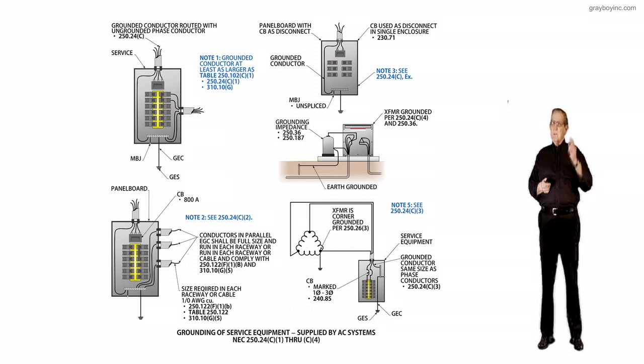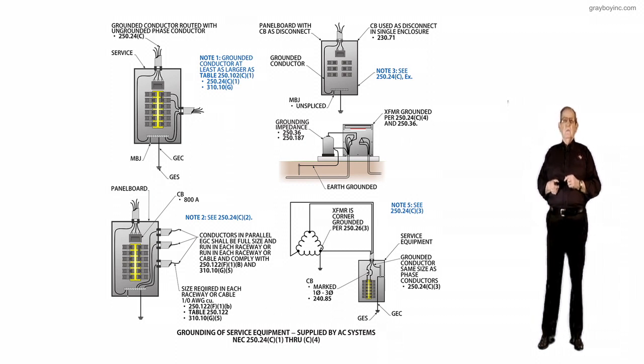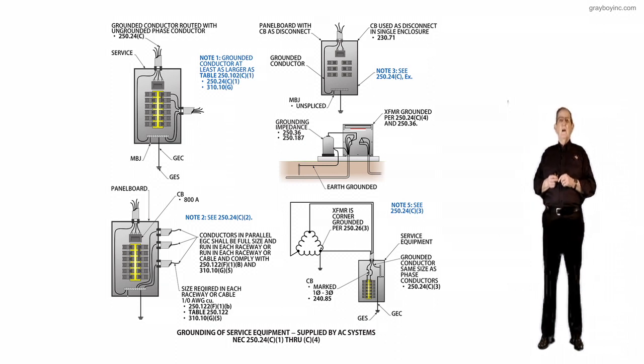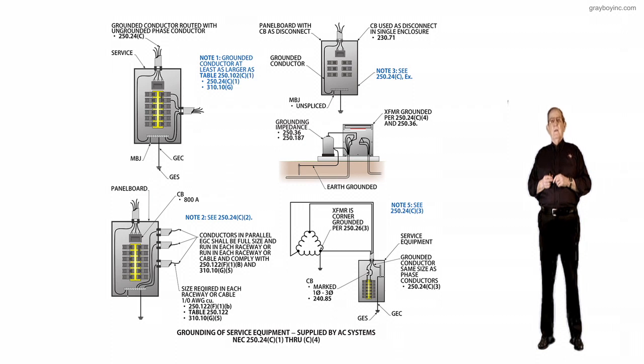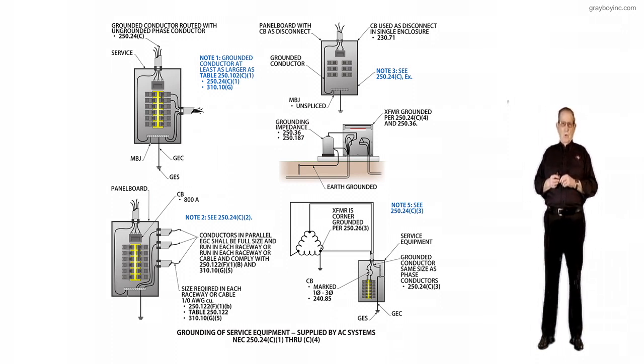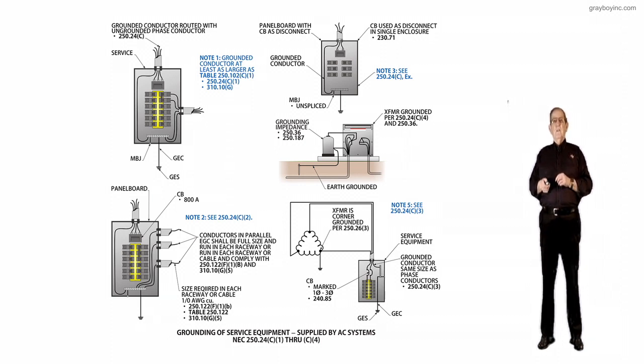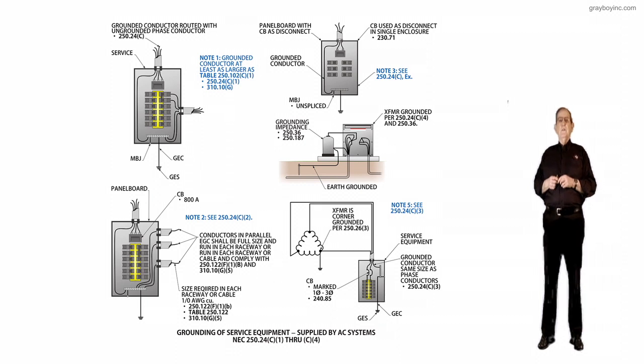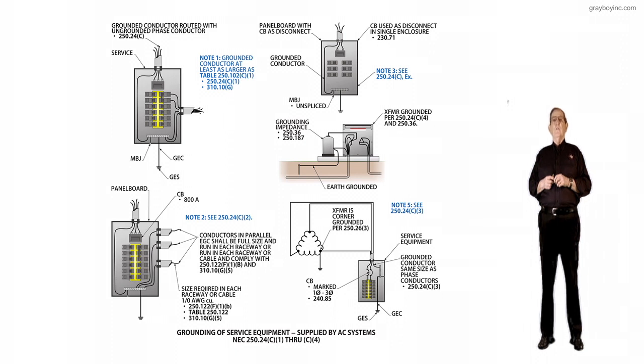Now, if my memory serves me correctly, if we have a 600 amp main, then those conductors would have to be probably about number 1 from Table 250.122 to serve as an equipment ground. If there were neutrals there, they would have to be at least 1/0 or larger. And then at the very bottom of the illustration, it shows you the size required in each raceway or cable: 1/0 or larger if you're dealing with the grounded neutral conductor. But if it's an equipment ground, then 250.122(F)(1)(b) and Table 250.122, and 310.10(H)(5) and (G) would regulate that installation to make sure all the conductors were sized properly.